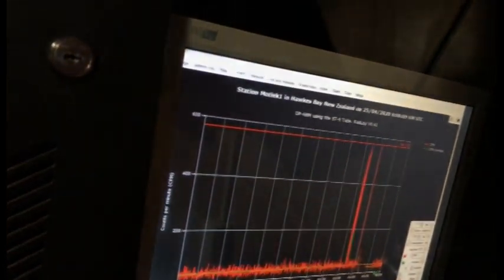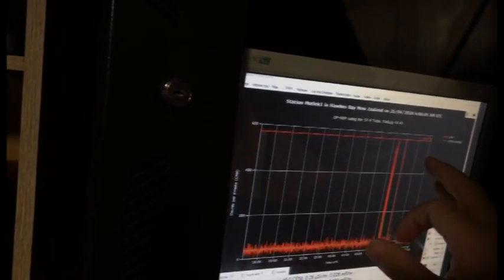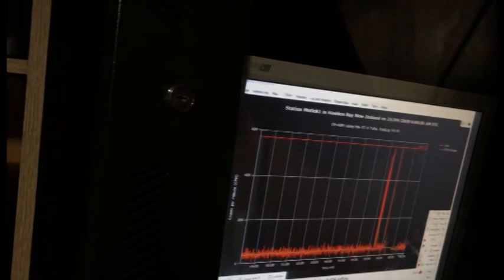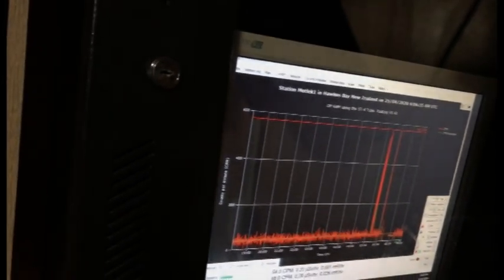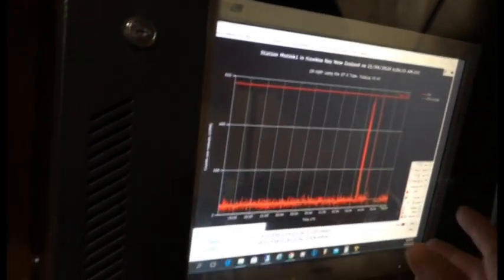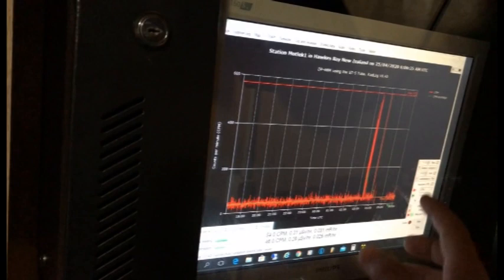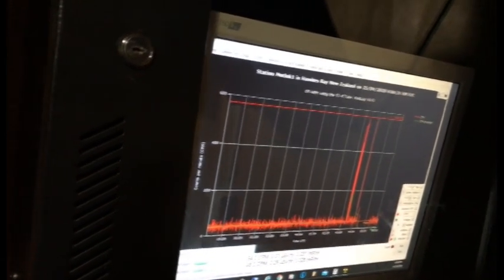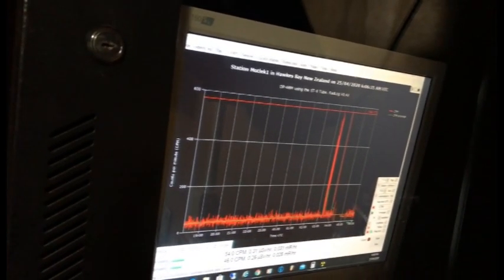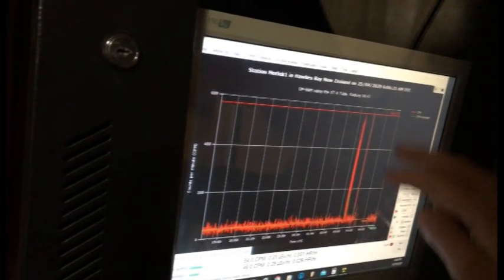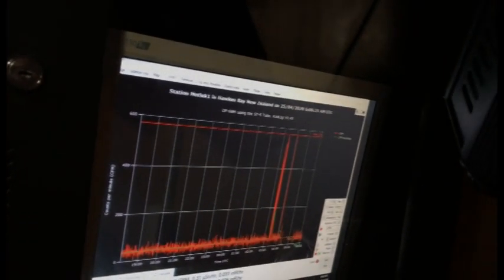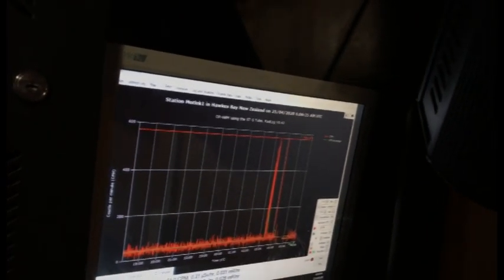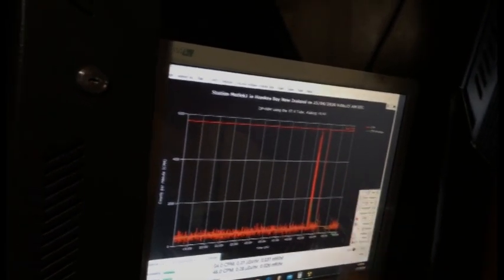And Geiger counters don't actually measure X-ray radiation correctly. They become overwhelmed, it's a lot more than they say it is. If you want to accurately measure X-ray radiation, you're better to use an ion chamber. So this is just a rough reflection, just saying roughly how much has been put out. Obviously I'm nowhere near the room when these occur.